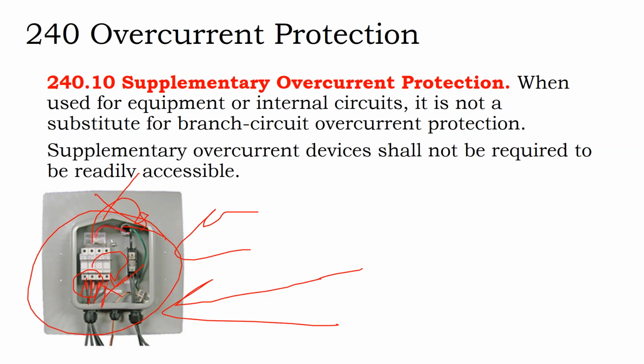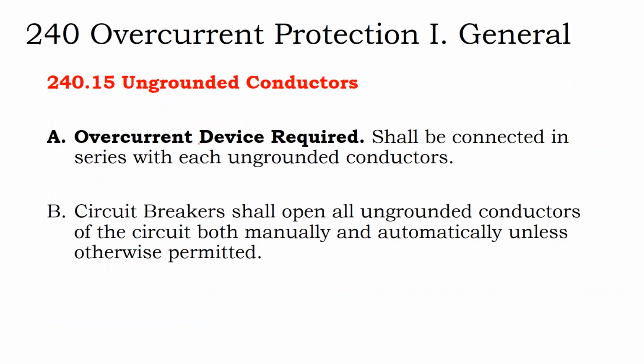At the same time, they're not subject to the same requirements. That readily accessible main overcurrent protection device does not need, your roof-mounted combiner box does not need to be readily accessible simply because it has breakers and fuses inside of it. It needs to be accessible, but not readily accessible. You might need a ladder to get up on it. You might need a screwdriver to get rid of the panel that's covering it, or to take the lid off and access it. It's still accessible. It's just not readily accessible. But your roof-mounted equipment does not need to be readily accessible, as long as there's a main overcurrent protection device elsewhere.